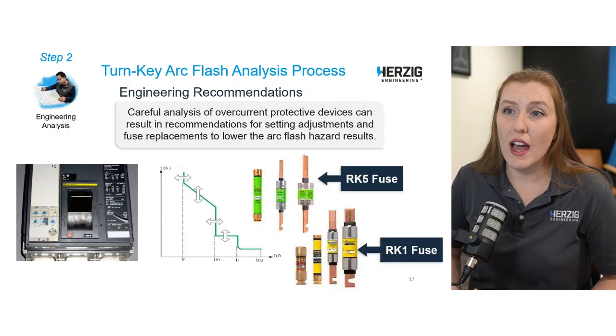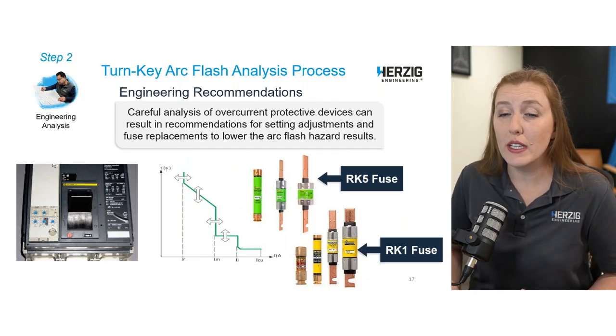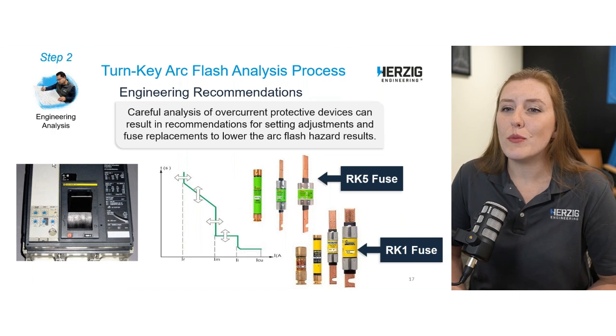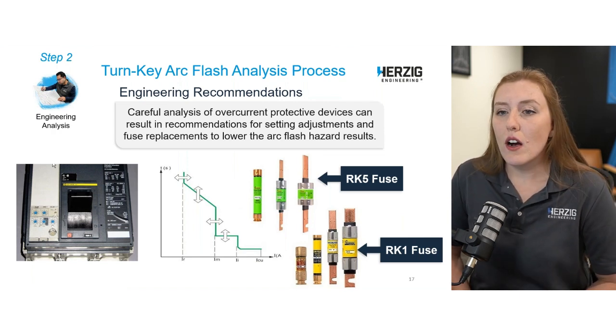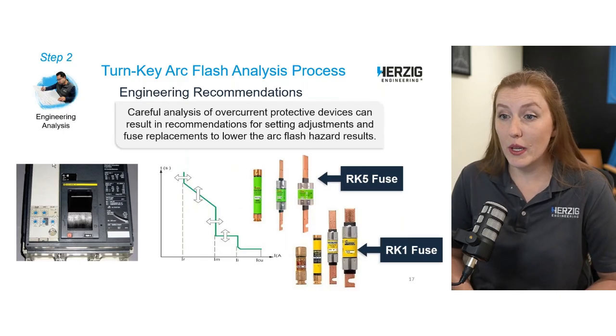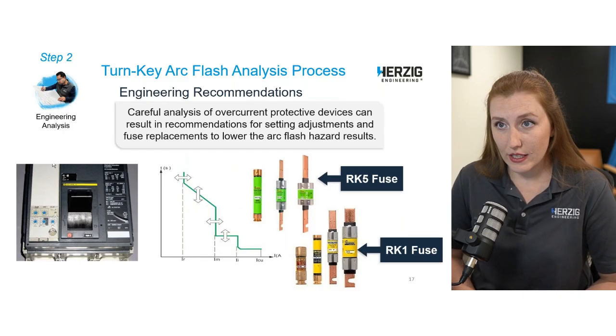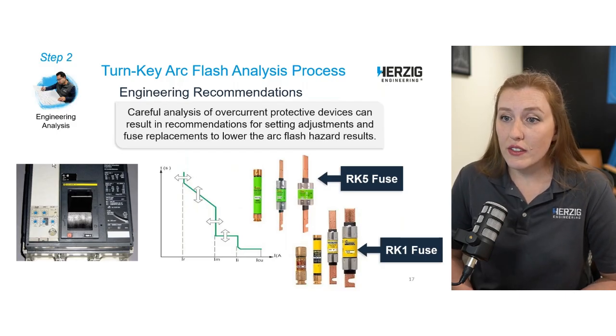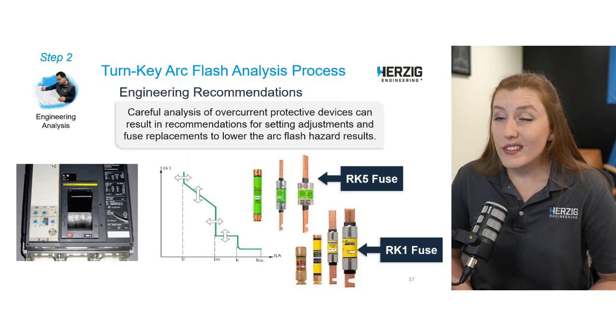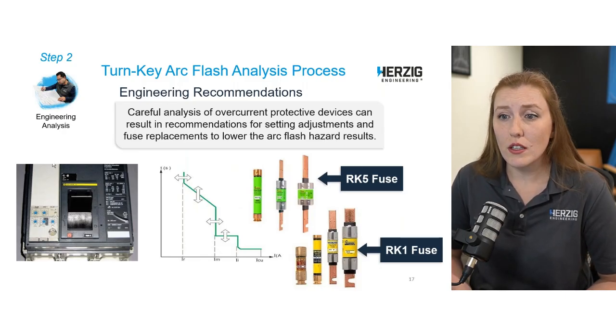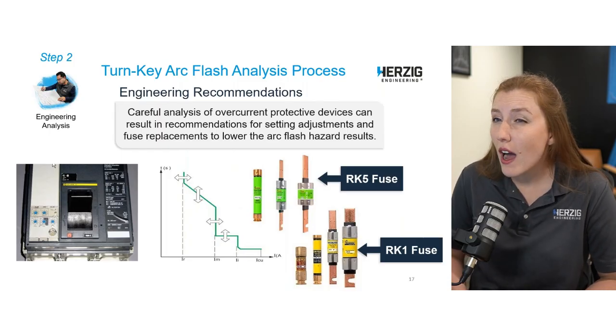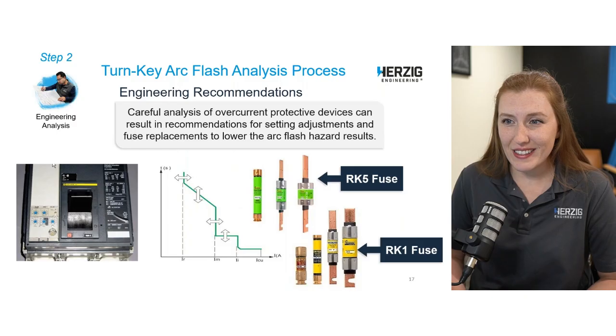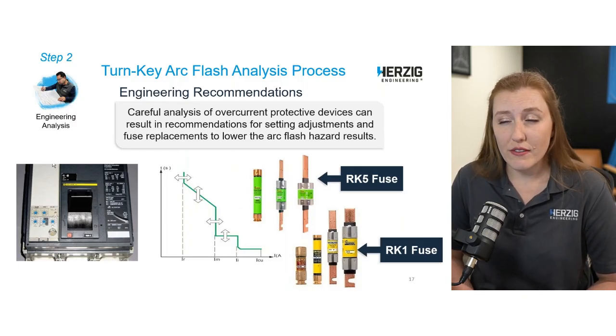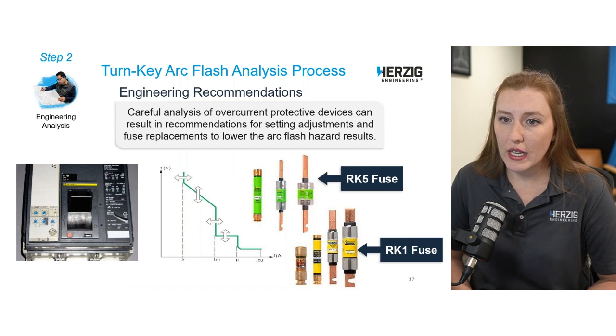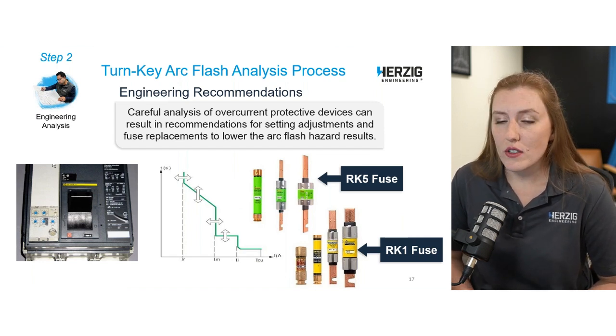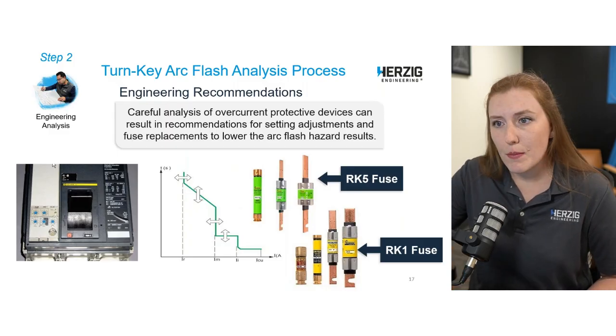One of the benefits of having a professional engineer that really knows what they're doing perform the actual calculations is that we can also provide recommendations to lower the hazards. There are a lot of really simple ways that can lower the arc flash hazards drastically. So careful analysis of those overcurrent protective devices, your fuses and your breaker settings can often lead to pretty simple adjustments to lower those arc flash hazard results. I would not recommend going around and trying to just do it yourself by trial and error. It is very fine-tuned, very specific detail that they're looking at whenever they perform these mitigation recommendation reports, and coordination as well. It all goes hand in hand, but that's part of it.